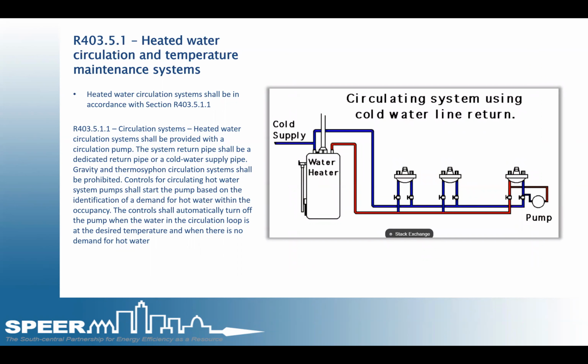R403.5.1, circulation system. These are not usually found in production homes, but you see them on larger custom homes. Different configurations are allowed, but gravity and thermosiphon systems are not. They must have controls that can turn off the pump when the water temperature is satisfied or there's no longer a need for hot water.